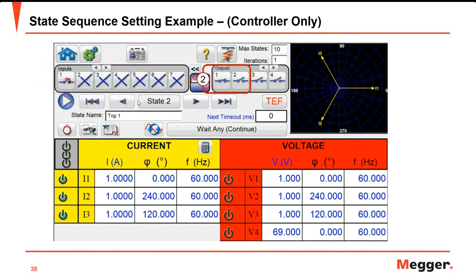Set the binary input — in this case we use binary input 1 for the trip output. Then set the binary outputs to simulate the breaker status. Note that this example is for testing the controller only. Here we use the binary output of the SMRT to simulate the closed position of the breaker.